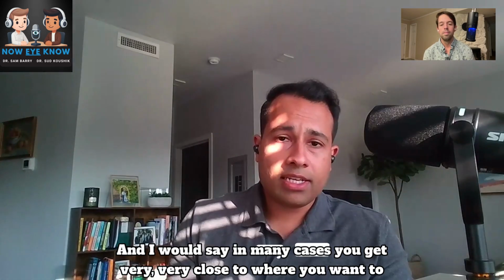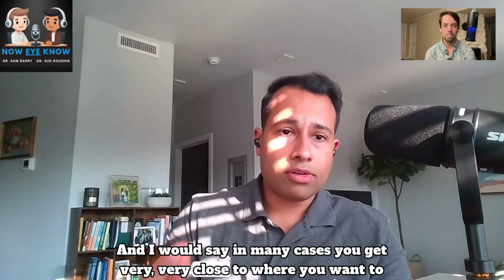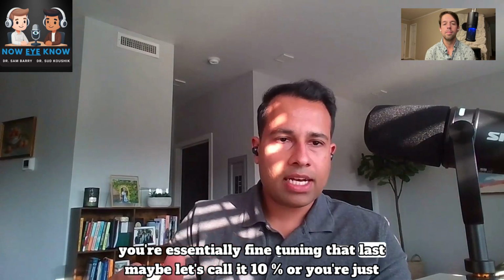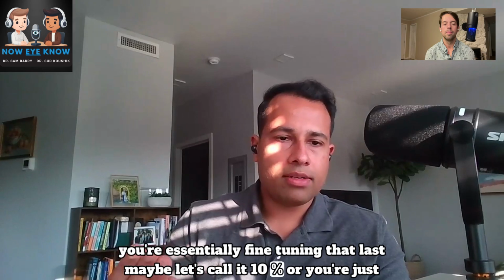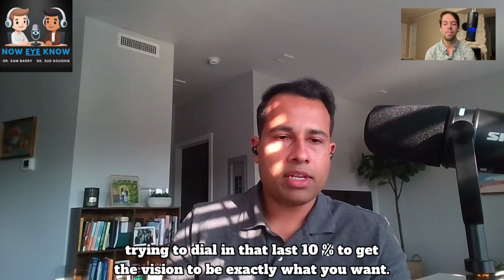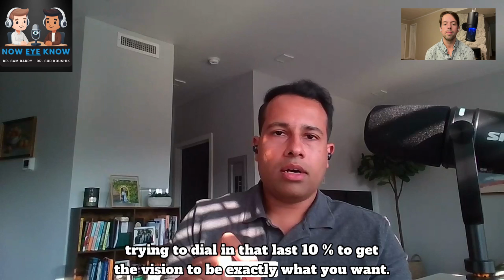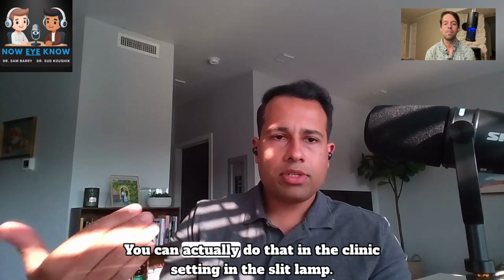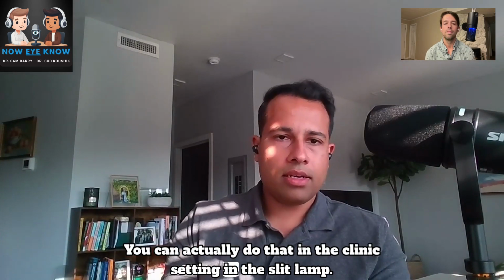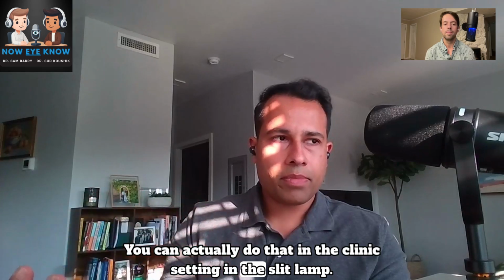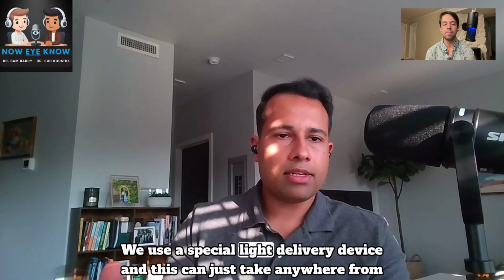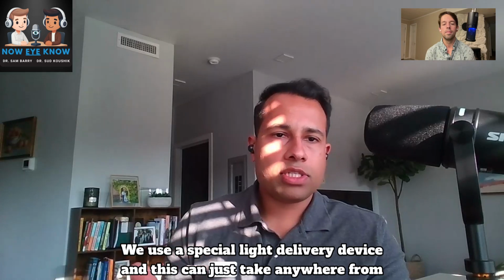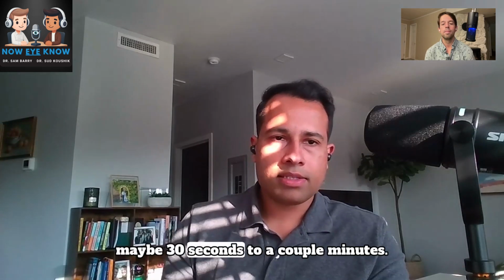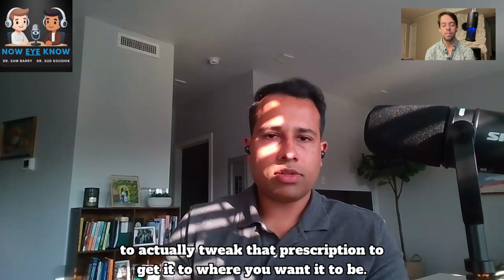In many cases, you get very close, and then you're fine tuning that last 10%, dialing in the vision to be exactly what you want. You can do that in the clinic setting, at the slit lamp, using a special light delivery device. It can take anywhere from 30 seconds to a couple minutes to tweak the prescription to where you want it.